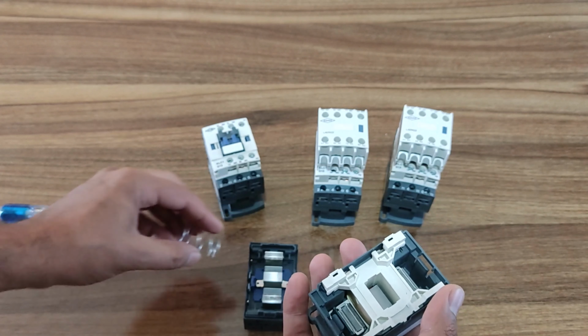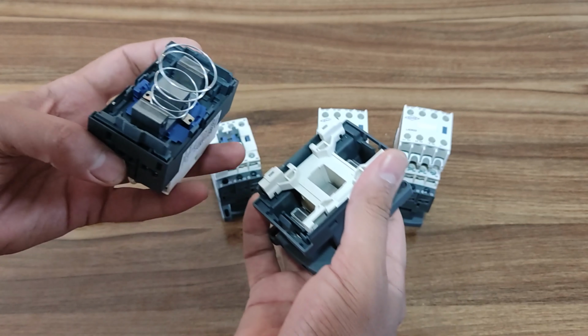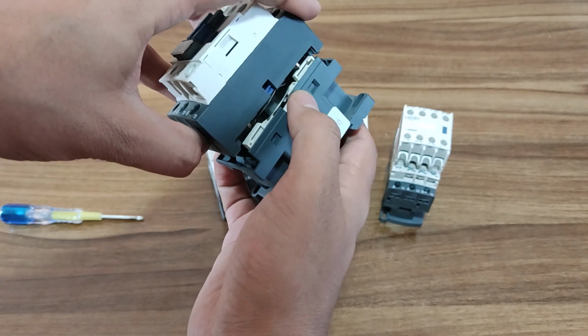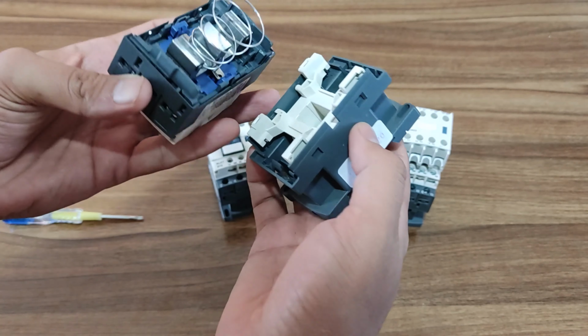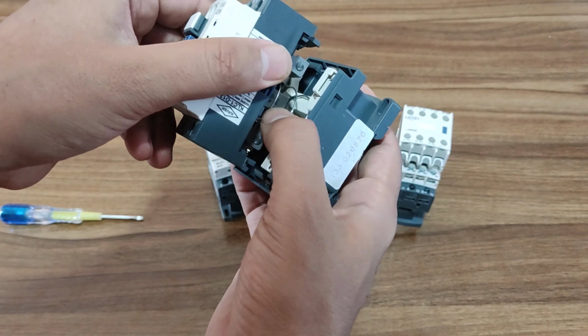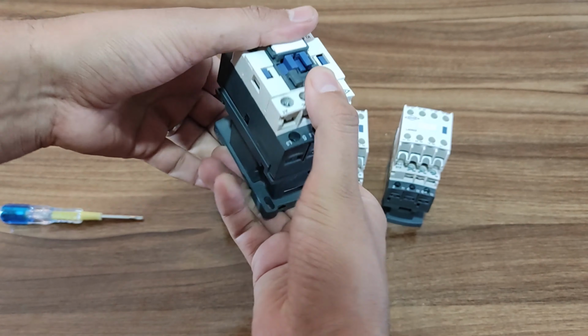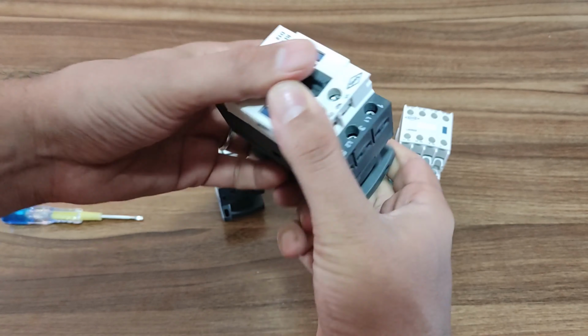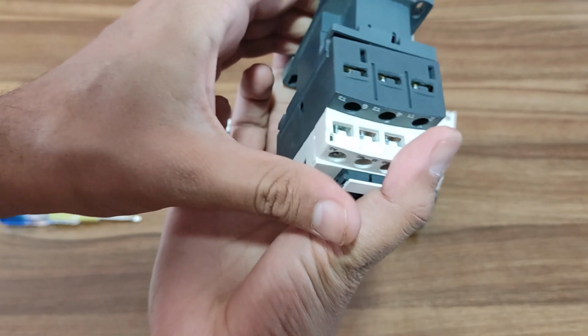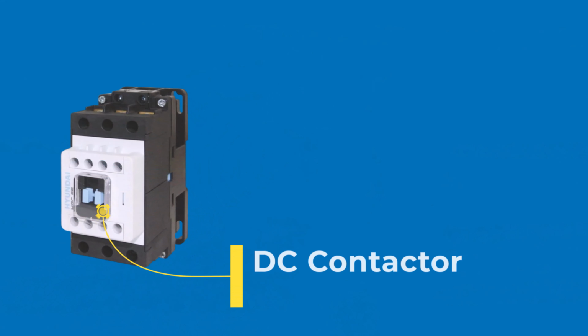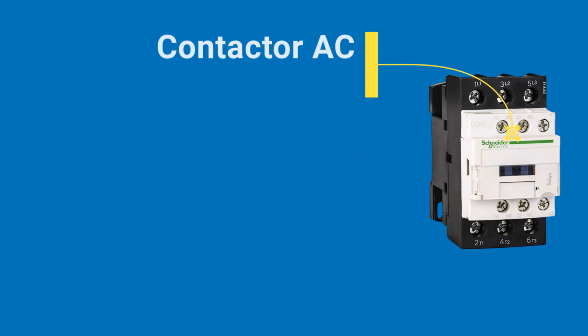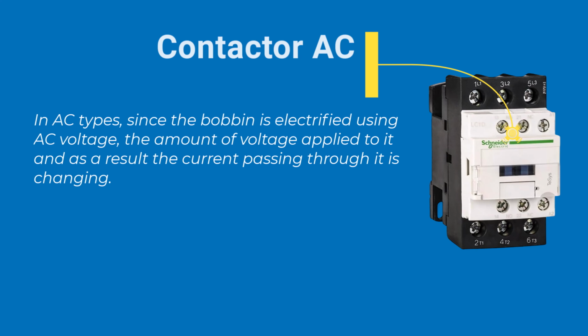or open. When the bobbin power is cut off, the moving core is returned to its previous state by a spring and the circuit is cut off. Contactors are made in AC and DC types. In AC types, since the bobbin is electrified using AC voltage, the amount of voltage applied to it and as a result the current passing through it is changing.